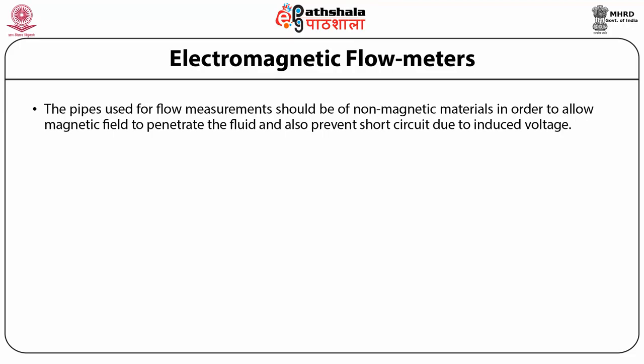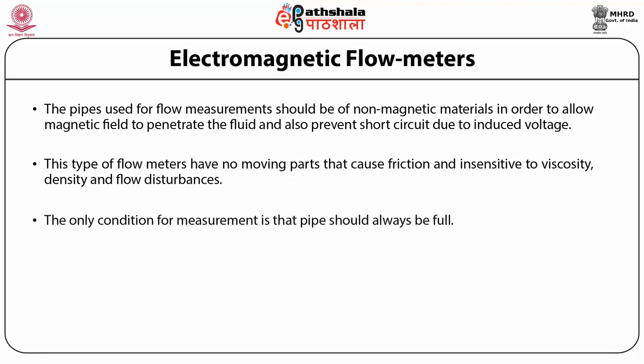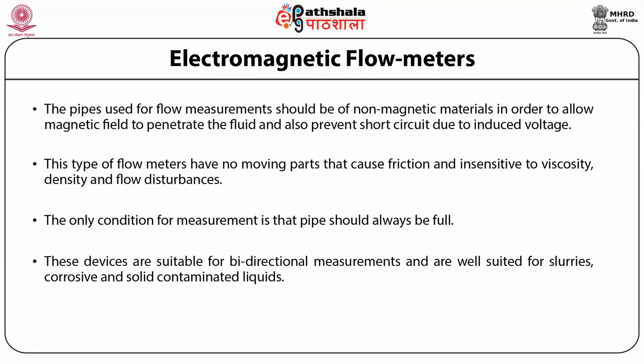The main advantage of electromagnetic flow meters is that they do not obstruct flow, so there is no pressure drop. They have no moving parts that cause friction and are insensitive to viscosity, density, and flow disturbances. They have a wide linear range of 10:1 and are independent of the fluid's properties except for electrical conductivity. The only condition for measurement is that the pipe should always be full. These devices are suitable for bi-directional measurements and are well suited for slurries, corrosive, and solid-contaminated liquids.